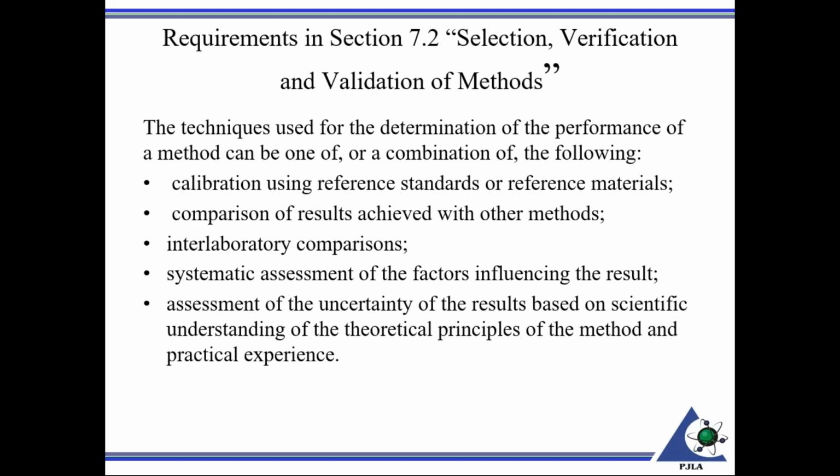Comparison of results achieved by other methods. Perhaps an interlaboratory comparison. Do the testing, send it off to another organization that is performing the same test. Systematic assessments of factors influencing the results. It could be things like volume dispensed or temperature or humidity fluctuations. And assessment of uncertainty of the results based on scientific understanding of the theoretical principles of the methods and practical experiences.